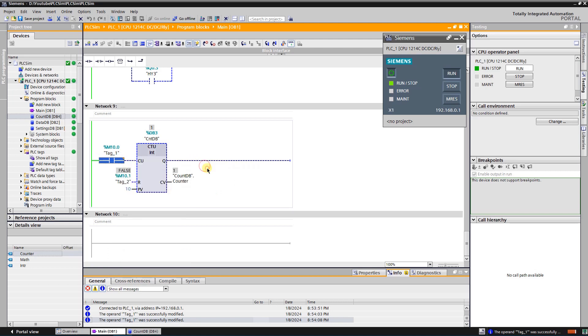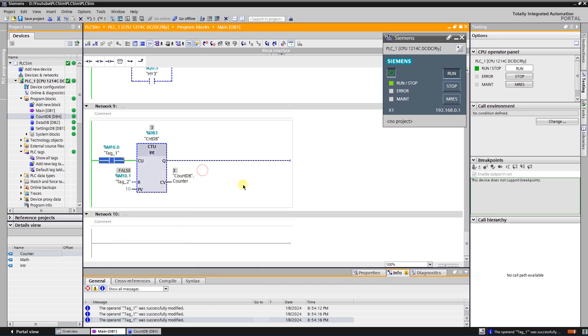As you can see, counter value increments when I trigger the input of the counter. Also, I believe that you have noticed that it doesn't matter how long I do keep counter input triggered, the counter value increments only on the positive edge of the input trigger.